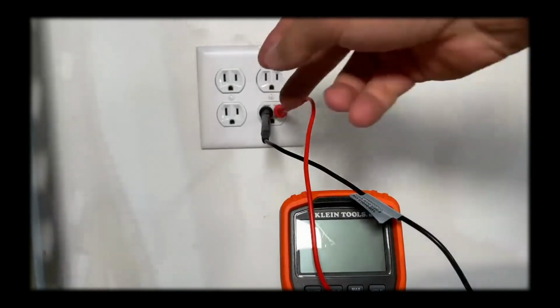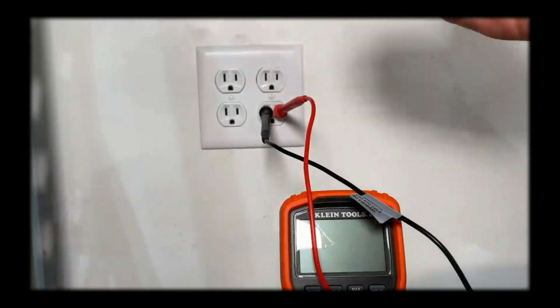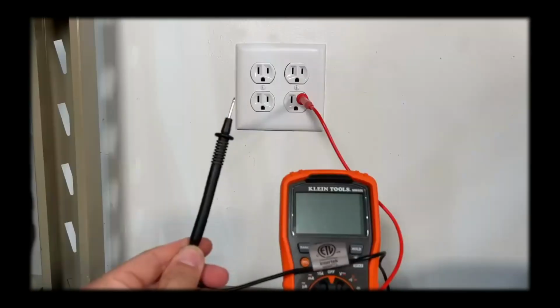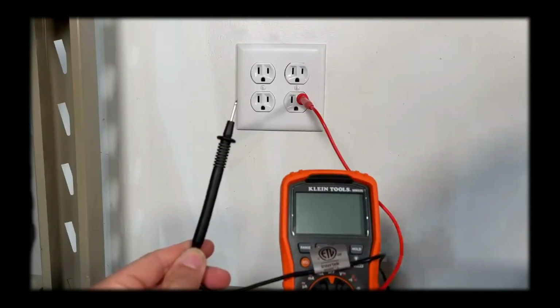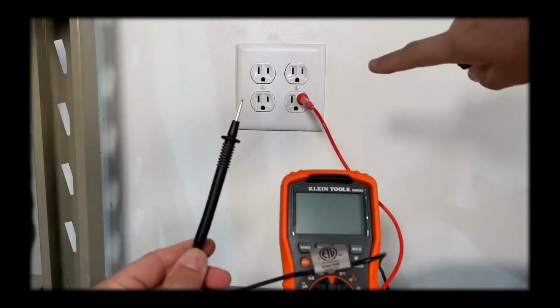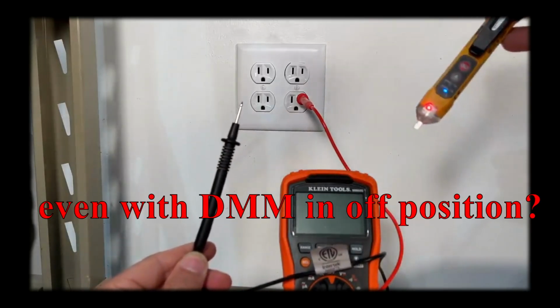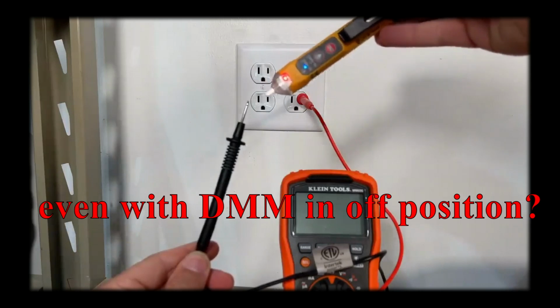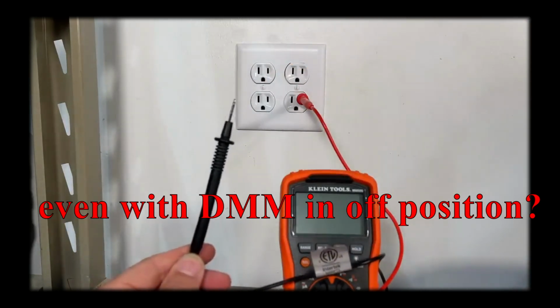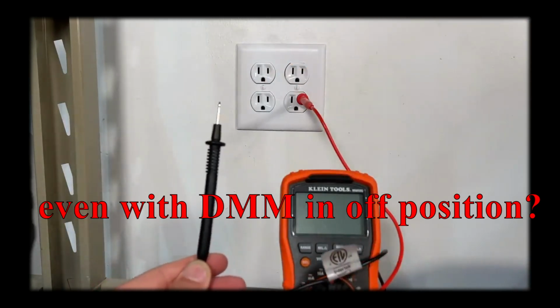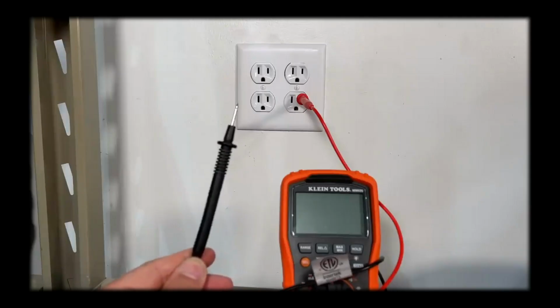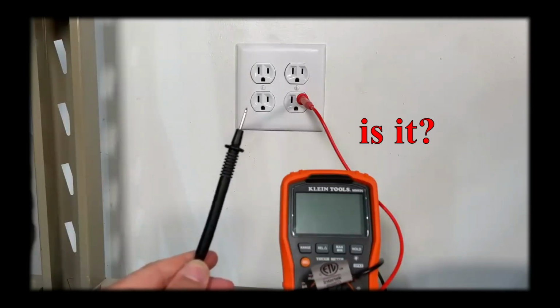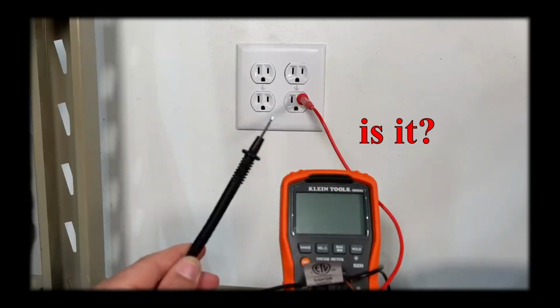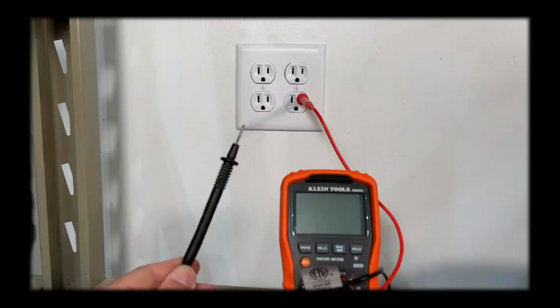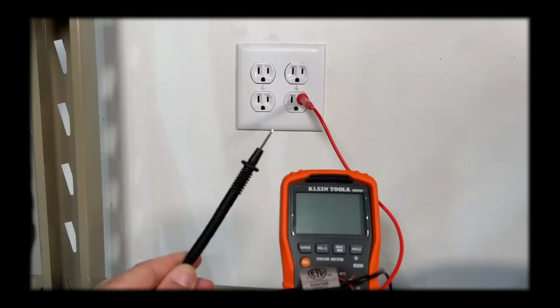If you do that, it can cause a safety issue, let me demonstrate. Even with the probe just sitting out here, because I have my hot side connected up, my non-contact voltage tester indicates that this probe is live. That is equivalent to sticking a wire in the hot side, and now it is live and can arc against anything that would ground it.